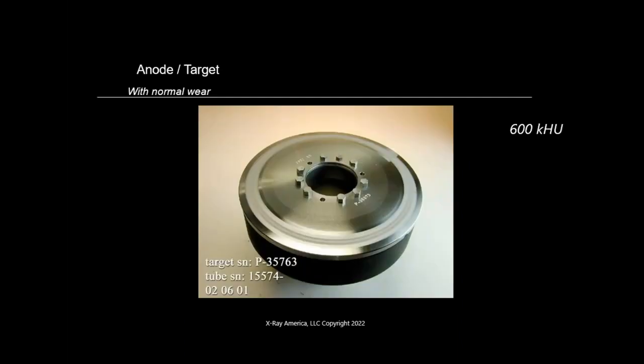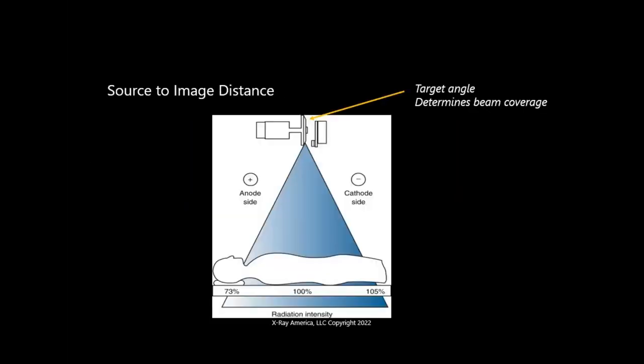So in this anode, and the anode that we're passing around, you see that it has an angle. There are different angles depending on your SID. When the beam hits the target, the angle depends on your SID, source to image distance, and what you need. If you have a small SID, you need a wider, bigger angle. If you have a higher SID, you want a smaller angle. But also, there's the inverse square law. The dose of radiation is an inverse square of the distance. So if you double the distance, you quarter your dose. So it's very important to understand your SID in the system.